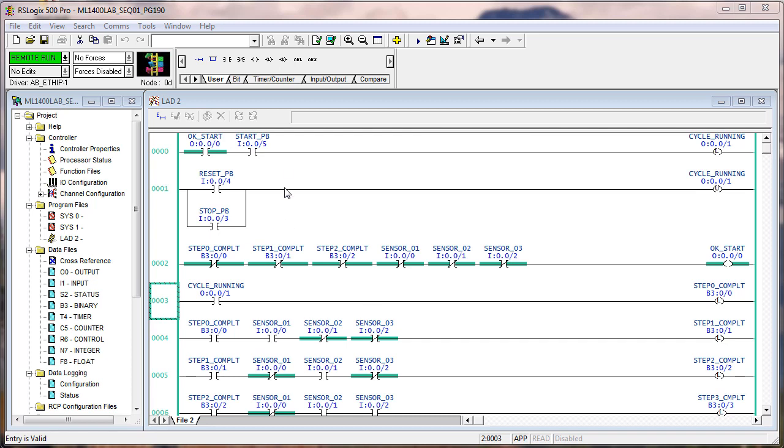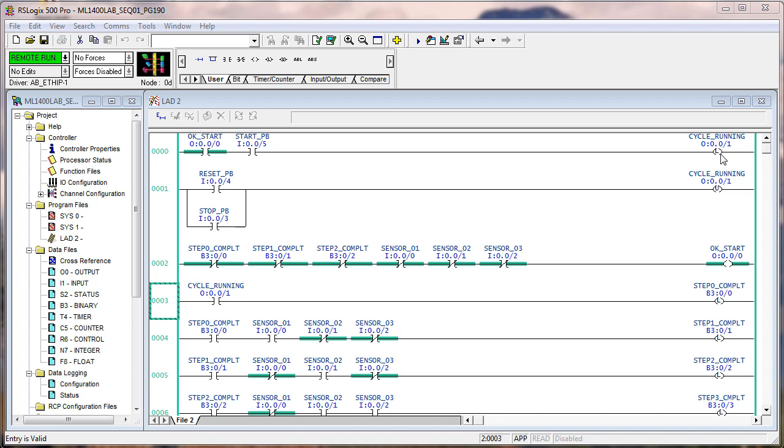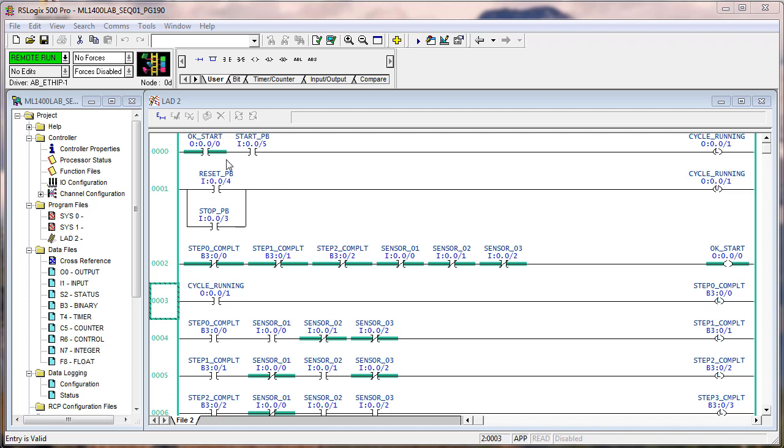The next thing we did, we added these two rungs of logic. Again, we're using latch and unlatch. If it's okay to start and you push the start button, then it latches a bit. And we're using the lights just so you have something to see, give you a little action. Latches the bit output zero one, in other words output one. And we use output one down here to complete step two. So we basically took out the okay to start, start push button from down here, put it in this rung. And we're using that bit here. And now we've got the reset button and the stop push button. Both unlatch and cycle running.